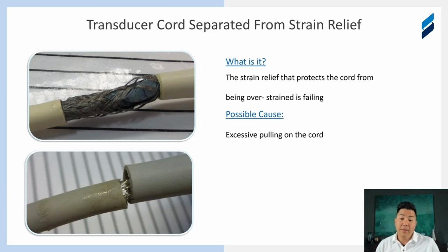over time. And the main problem here is that the outer protective layer is separated, like you see in the picture here on the top and the bottom, and it now exposes all the electronics to the external world. And when we're looking at protecting the electronics, this is a huge compromise to all those microcoaxial lines on the inside. We are exposing the braided metal that keeps things together, but it also acts as a ground. And on top of that, you can see on the top picture here, right here, that isn't shiny metal. That's actually, over time, this hasn't been addressed, and now there's corrosion taking place, likely from some gel getting on there.